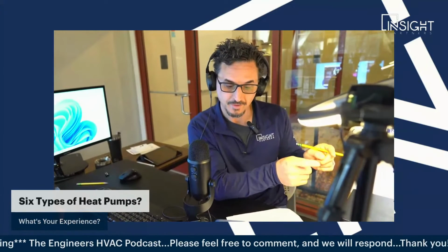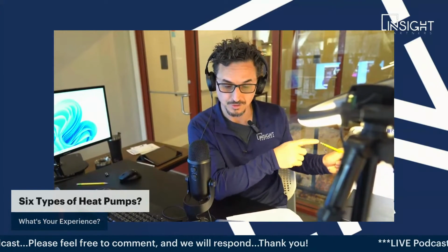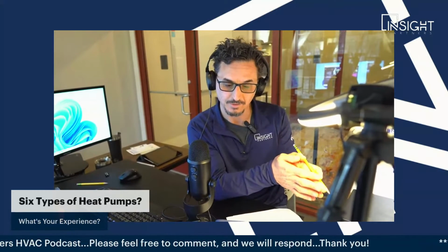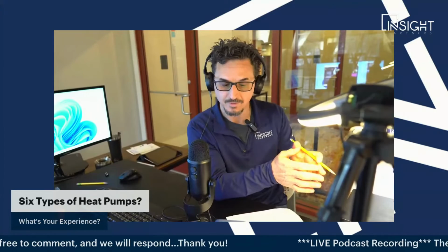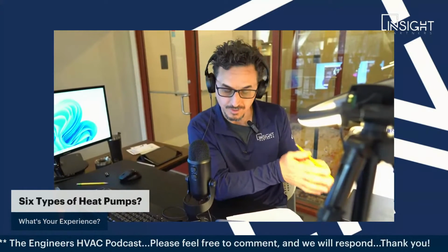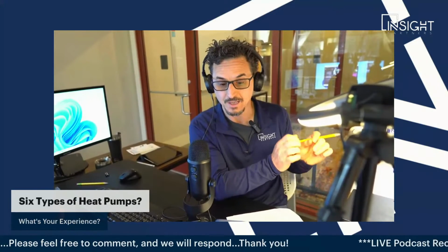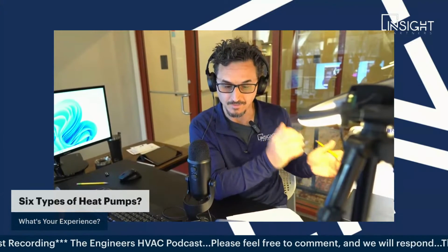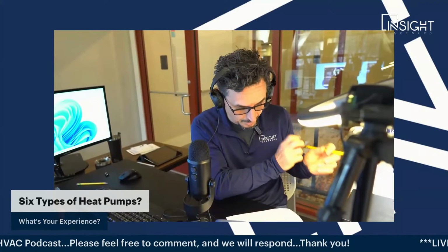Okay, so VRF heat pump. Now VRF heat recovery is a whole different story. This doesn't really go along with the heat pump discussion, but I just want to mention it. VRF heat recovery is when you can have simultaneous heating or cooling. So if you go back to the previous example of one condensing unit connected to 20 indoor units, you can have 5 of them heating and 15 cooling, or 10 heating and 10 cooling, any combination of cooling and heating you want. That's VRF heat recovery versus just the heat pump system. So if you're doing VRF heat pump only, be aware that all the units are either heating, some can be off, or they're all cooling and some can be off, but you can't have simultaneous heating and cooling. Be careful of that, because it could get you into trouble.